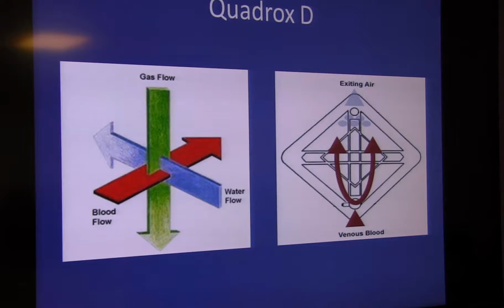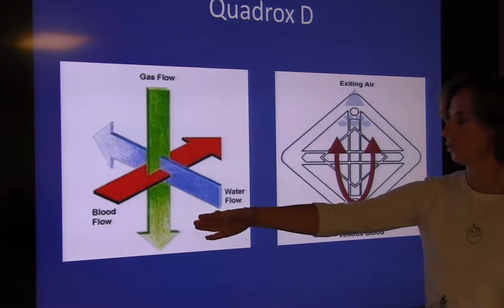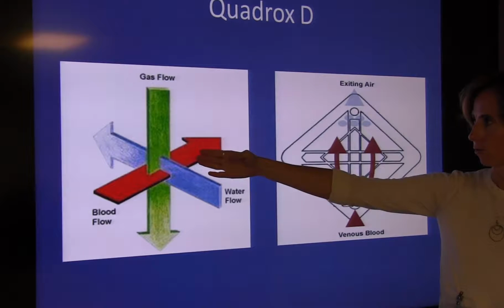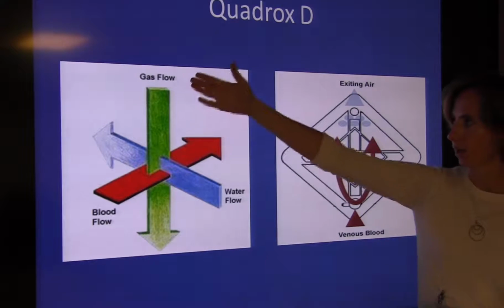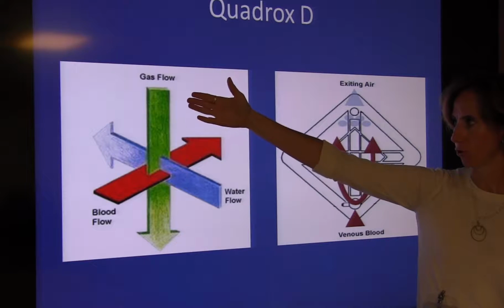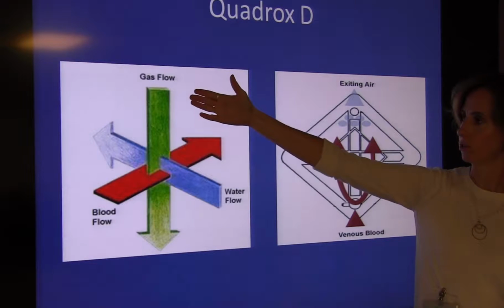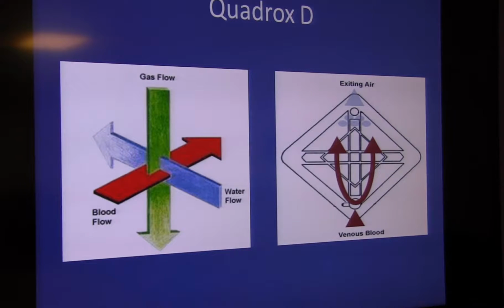And this is why it's confusing, is because what you have is 3 different things going through it. So if you've got blood flow going front to back through it, you have to have gas flow that's running in countercurrent. And so the way the gas flow actually runs through this thing is from the top to the bottom.